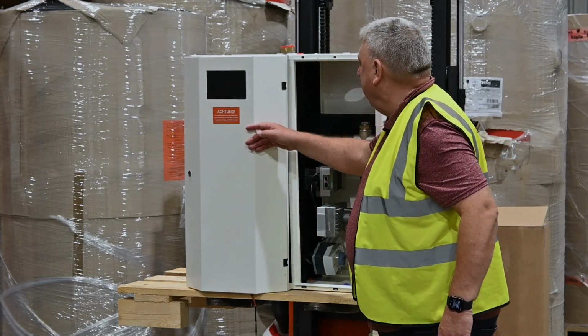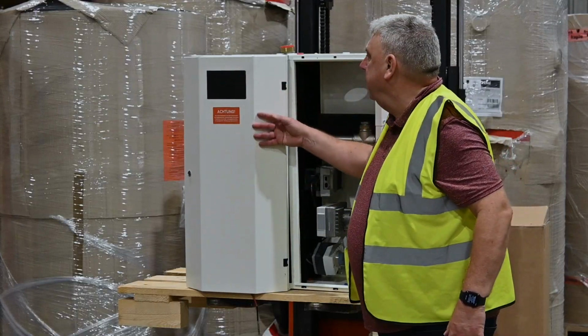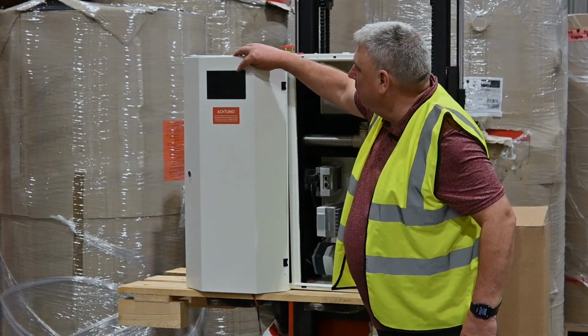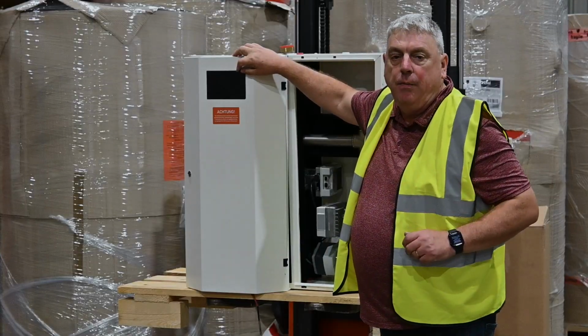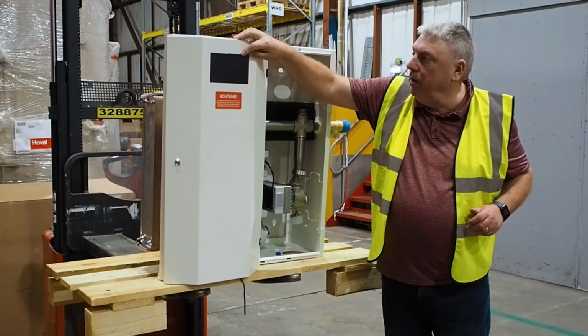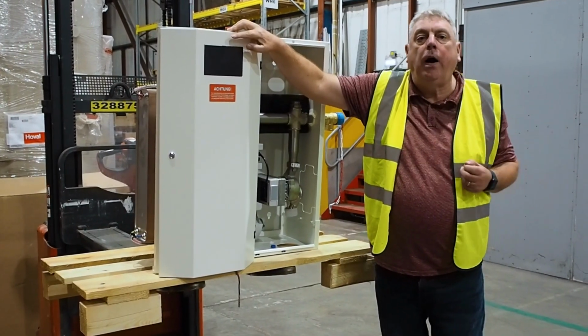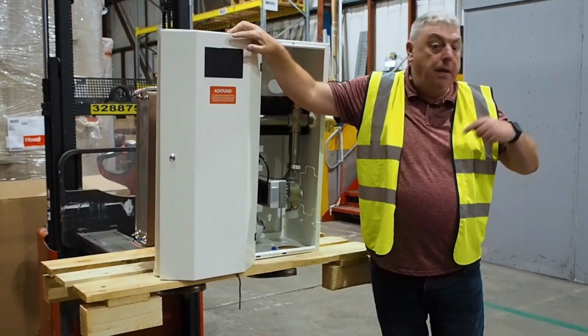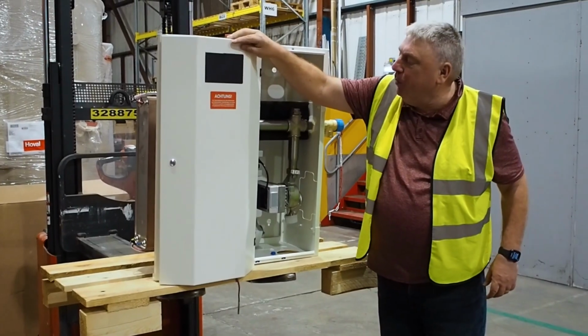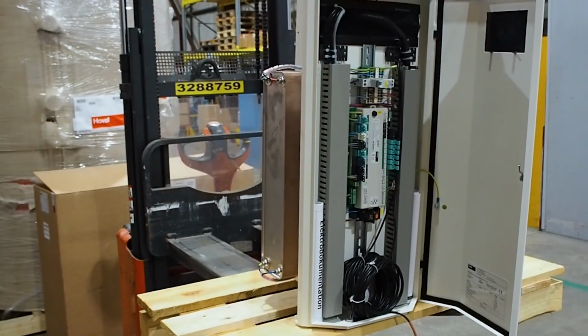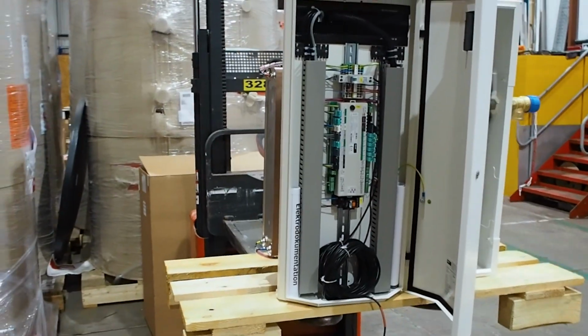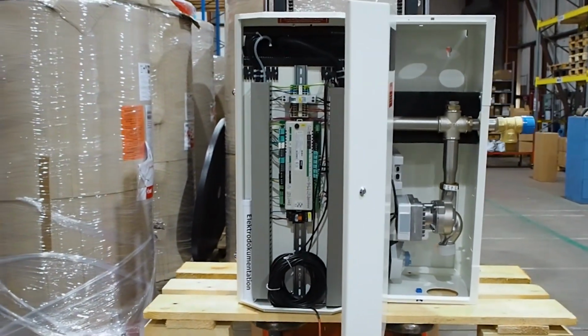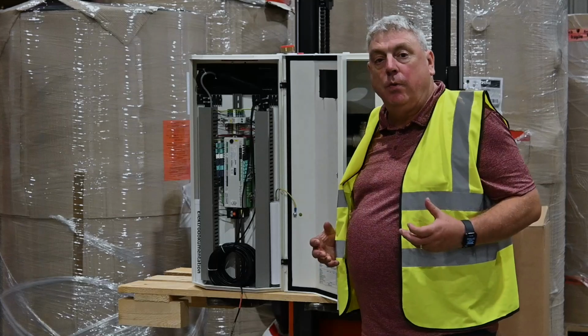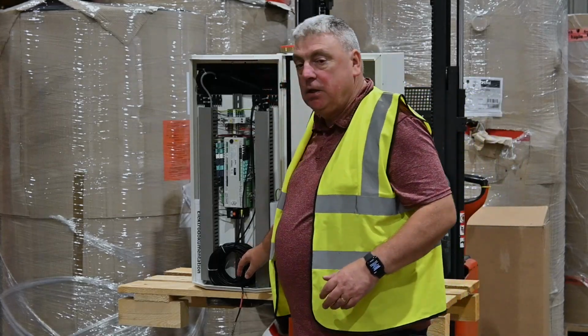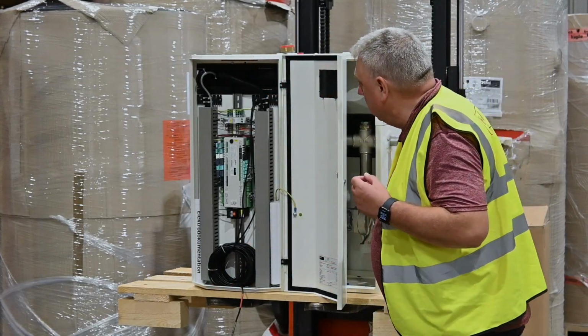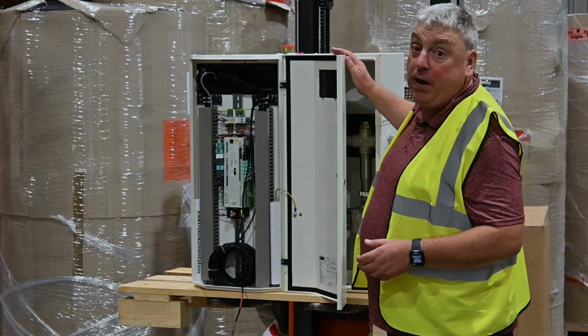If we look now very quickly at the control side of it, it's all inbuilt into the unit. On the top here, we'd fit a touchscreen, an interface unit which sits in there. Obviously we don't want to put that on while we're transporting it, so it's in the box somewhere. Okay, but quick look behind here reveals the brains, if you will. We have a standard programmable piece of electronics which we parameterize when we set the thing up, along with a couple of sensors which will go into the storage vessel, and really that's about it.